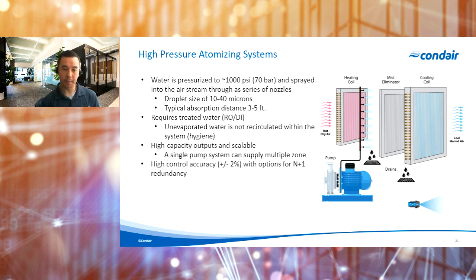Now, the big difference here between evaporative media systems and a high pressure atomizing system is on that control side. So as soon as we have a demand for humidification or cooling, the pump will turn on and we will start spraying water. As soon as we hit that point, we'll turn the pump off and we'll stop spraying water. These systems are also capable of staged control or modulating control. So with this type of system, we're able to achieve accuracies in the range of plus or minus 2% on the discharge side, in comparison to, say, an evaporative media system without any other kind of control schemes there. We're looking at probably plus or minus 5 to 10% control.